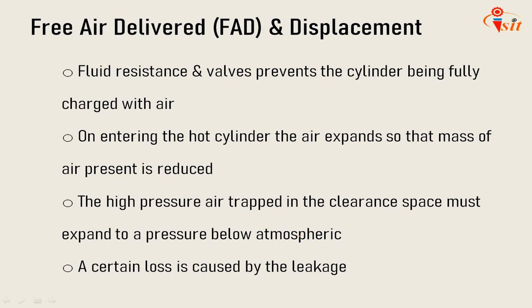Now the free air delivered per minute is less than the displacement of the compressor. There are certain reasons for it. First one is fluid resistance through the air intake and valves prevents the cylinder being fully charged with the air at atmospheric conditions.